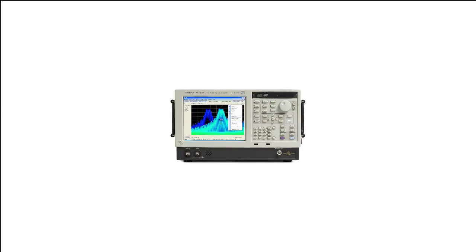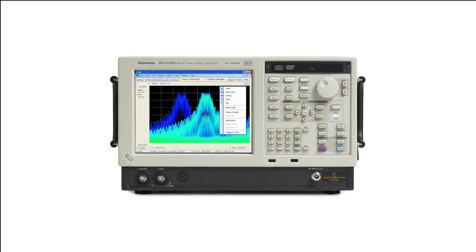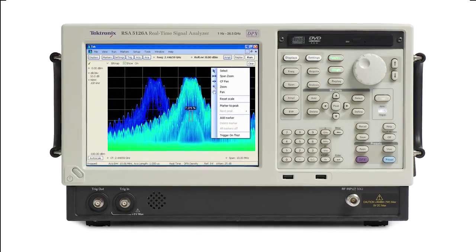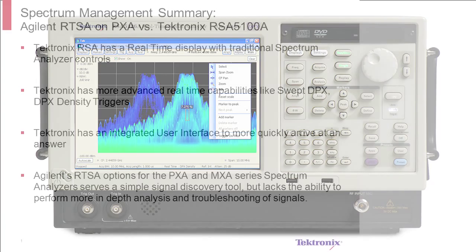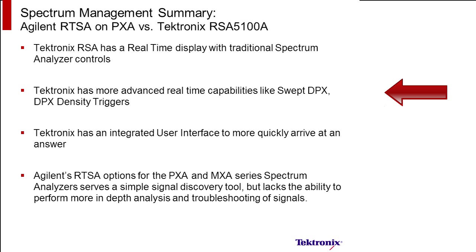Tektronix RSA has real-time display with traditional spectrum analyzer controls. So I have an ability to discover signals and then drive the instrument like I would a regular spectrum analyzer. Tektronix has more advanced real-time capabilities like swept DPX and density triggers that allow me to control the instrument like I would a regular spectrum analyzer when I'm using real-time displays, as well as trigger within the real-time bandwidth on any signal I see on the screen.